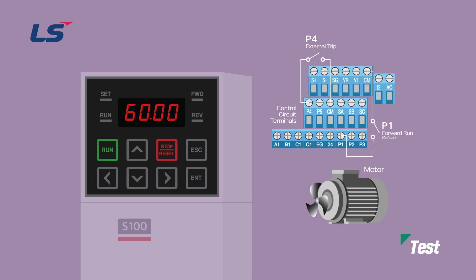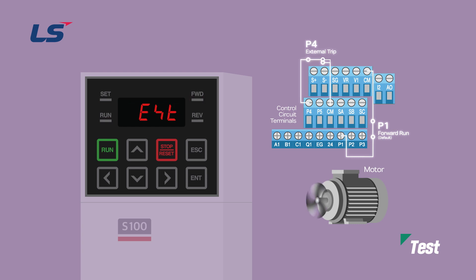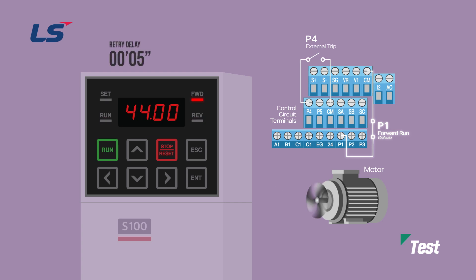Let's run the test with the parameters we set earlier. First, turn on the P1 terminal to run the motor. Turn on the P4 terminal to create a trip situation. When the trip message appears on the LCD keypad screen and the motor stops, turn the P4 terminal off. Since the external trip is a latch-type trip, turning the P4 terminal off will not clear the trip. Five seconds after the trip occurs, it will automatically reset, and the motor will run because the P1 terminal is left on.